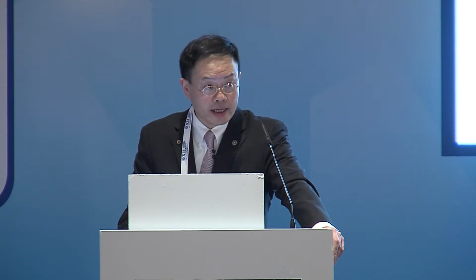In comparison between the previous US standards and the current ISO standards, the previous one had class 1 to 100,000, covering 5 classes, but the ISO standards add 3 more classes, and also include 1 micron as a size. If we plot them individually, the left is the US standard 209 and the right is the current ISO standard. If we overlap them to see the difference, we may realize that these two standards are not identical, but roughly equivalent on certain classes and particle sizes.